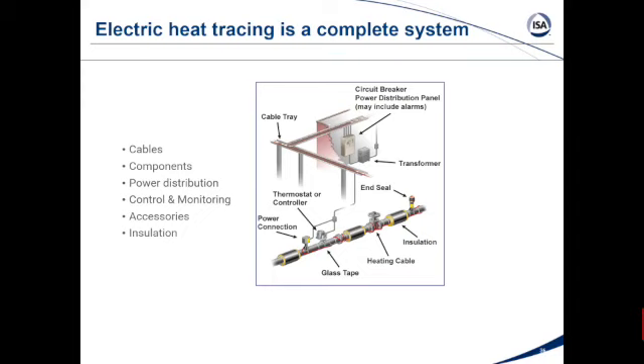We did a design. There's going to be numerous passes of cable, very high load because it's a high maintain temperature. And they said, well, this is crazy. This is going to be over $100,000 for only X amount of pipe. That cost per foot is just way too high. And I said, well, this is why we wanted to get involved earlier. And to give you an example, when we reran calculations for them, everything is exactly the same: the voltage, the maintain temperature, the minimum ambient, everything's the same, except we went from 1 inch to 2 inches of expanded perlite. We just increased that insulation thickness.